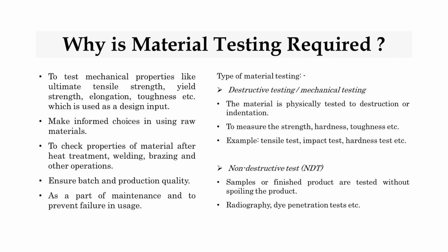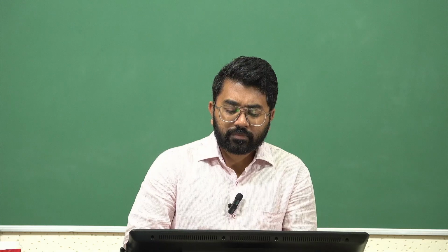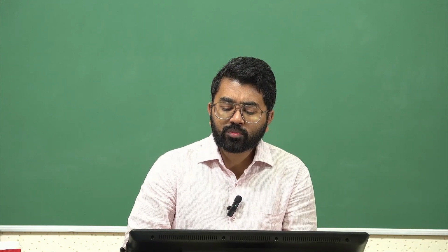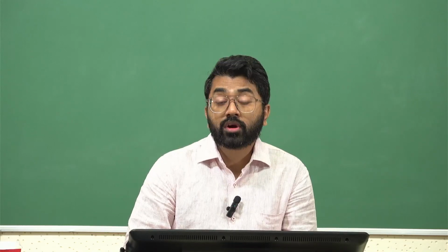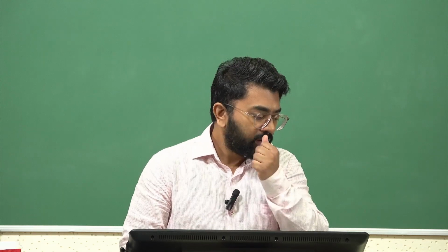Next type comes the non-destructive tests. So samples of finished products are tested without spoiling the product. So this is for biomaterials or implants. Let's say I have a nice absorbable stent which is going to go inside a particular artery, and I'm supposed to be testing this mechanically to those conditions where it will be within that artery, right?